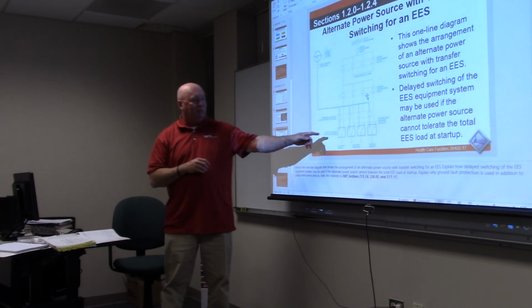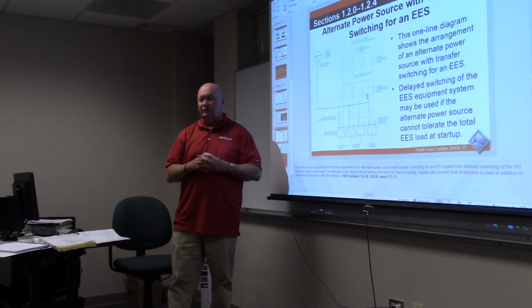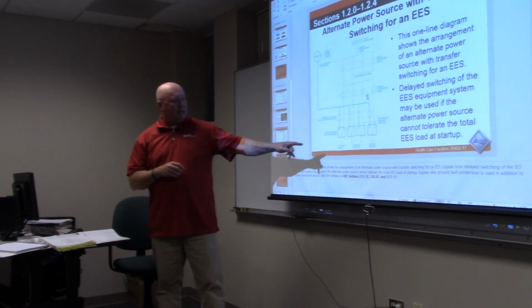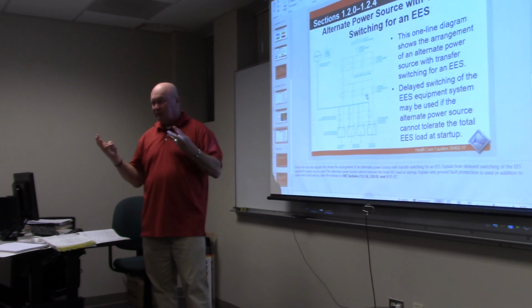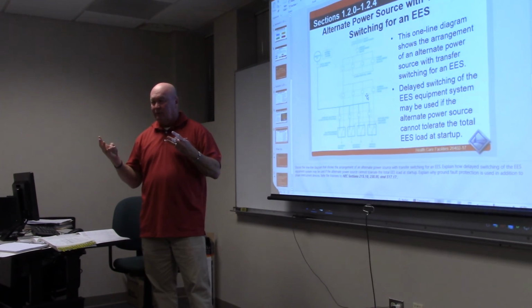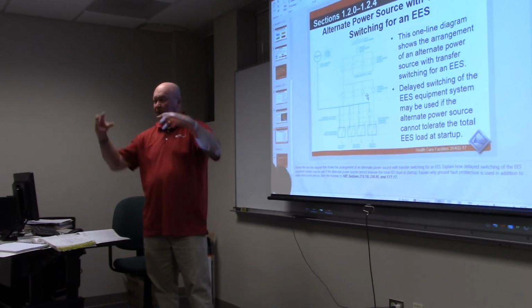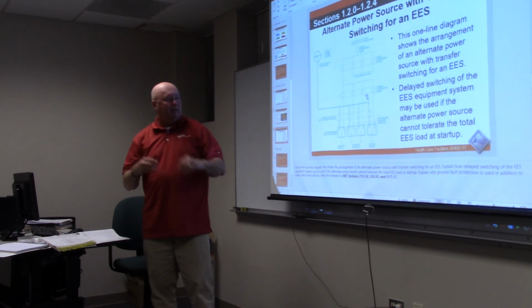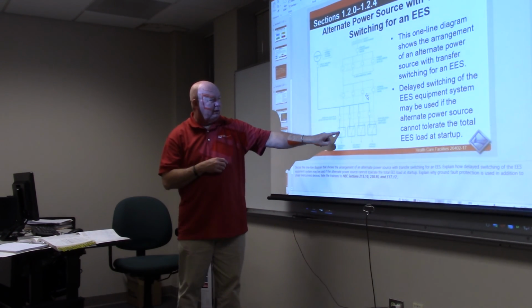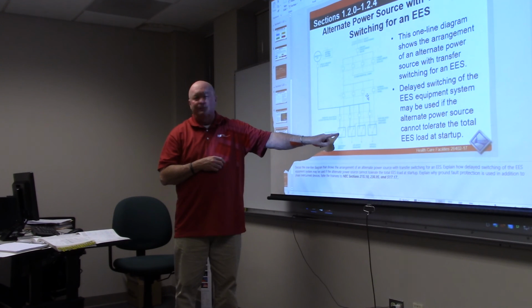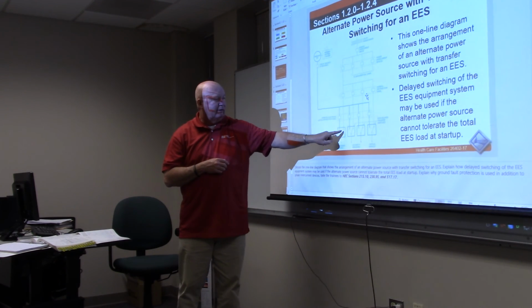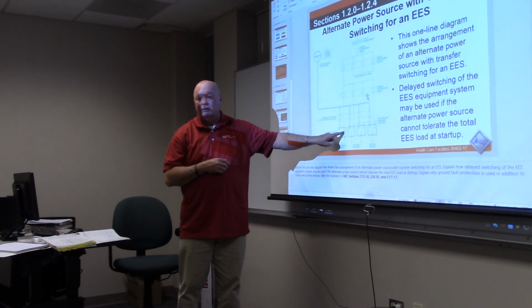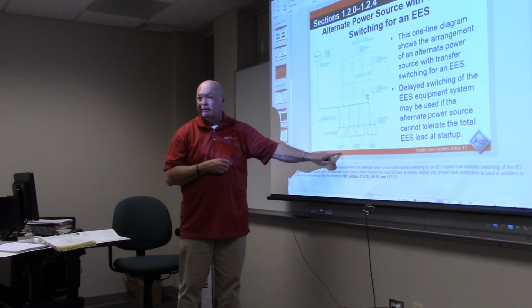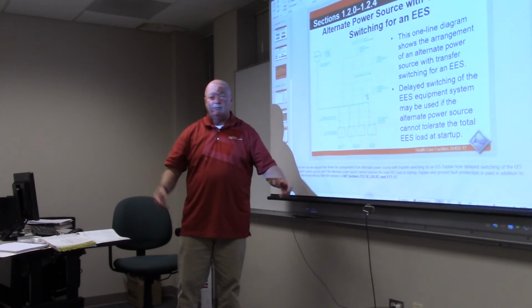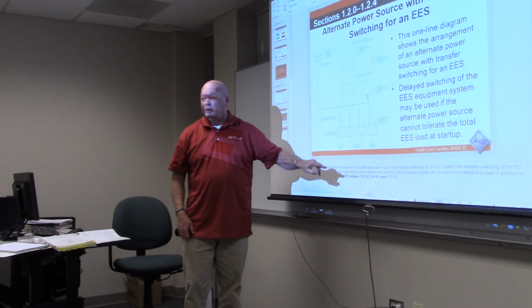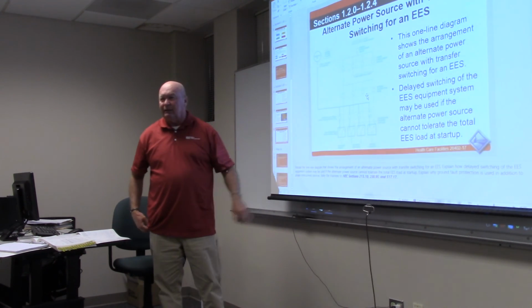There's a lot that goes into wiring this transfer switch, making sure you've got 3 connection points inside of it, right? 3 connections, 3 different feeders coming in. You're gonna have one coming from generator power, one coming from normal power, and then one supply going out. So you've got 2 lines and 1 load - you best be connecting this in the right place.